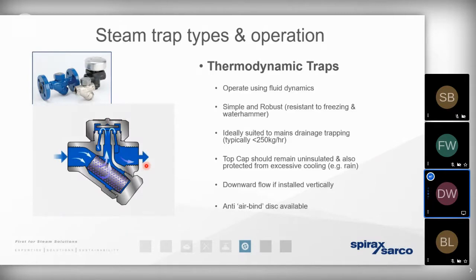But once the condensate gets to a temperature that's higher and higher, typically above 100 degrees, well, as that steam is pressurizing the condensate and pushing it down this narrow orifice, there's going to be a very small fall in pressure. And that fall in pressure is going to result in a small amount of flash steam. And remember, flash steam exists at a much greater volume than liquid condensate does. So that huge expansion is going to have an effect on manipulating this little disc in the head of the trap.